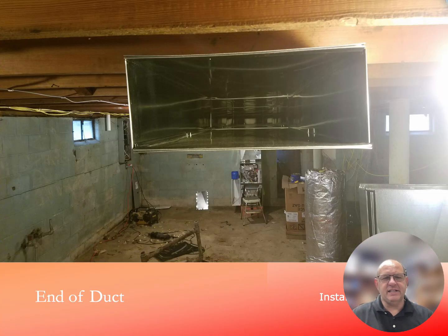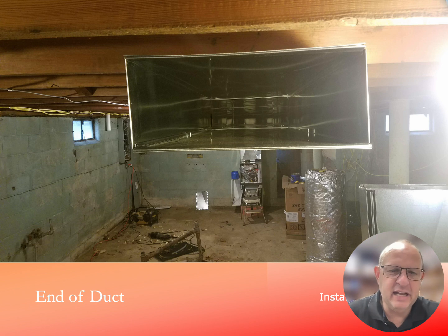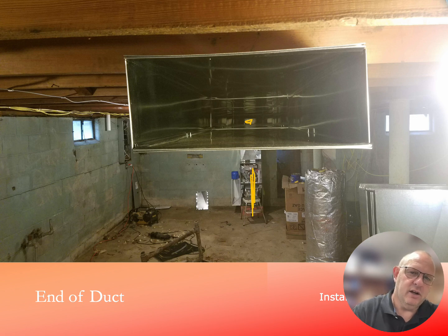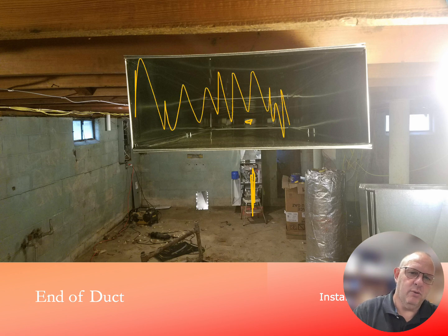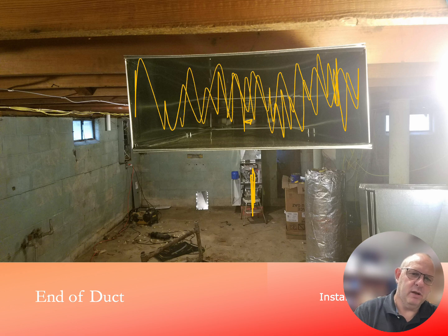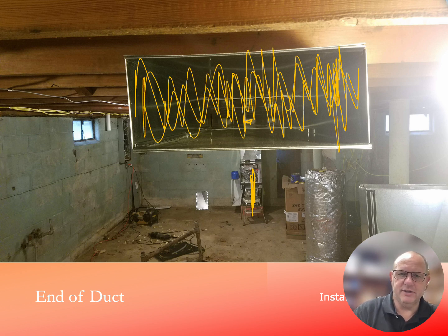Now, this is just an example of the end of the trunk, as we can see, running all the way down through the center. Right down there is our furnace. We can see our furnace right in this area here. In this location right here, I'm going to blank this off with a piece of metal that I'm going to call an end cap. It's going to stop that airflow and build all that pressure on that system.